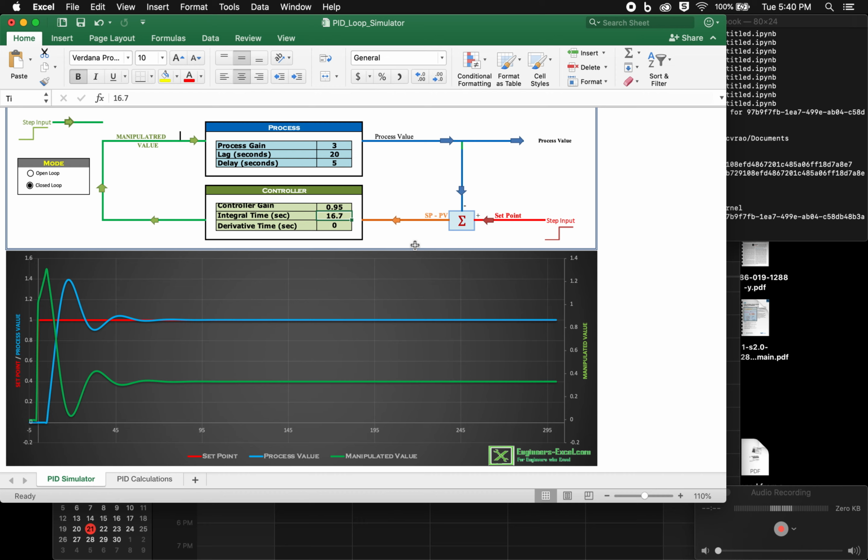I should also mention that there's lots of auto-tuning methods that a lot of PI controllers have built into them. So basically what these controllers will do is they'll start artificially introducing oscillations into the system. So it'll start oscillating the input. And then based on the response, you can back-calculate things like the ultimate gain, the period, and then use Ziegler-Nichols tuning or any other rule based on that information. And as I mentioned, there's lots of different rules for that.